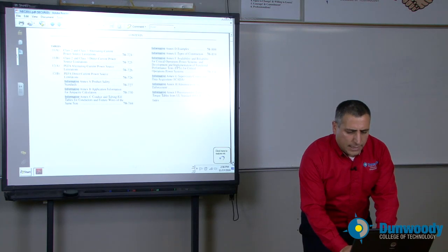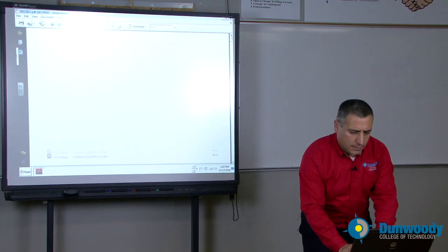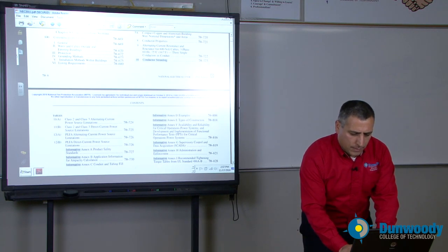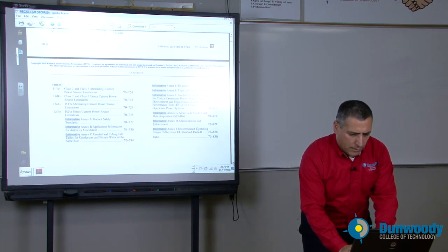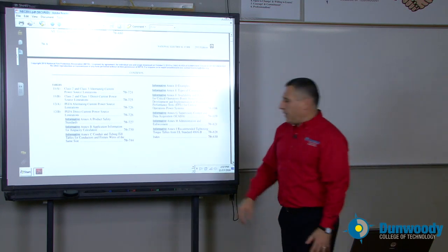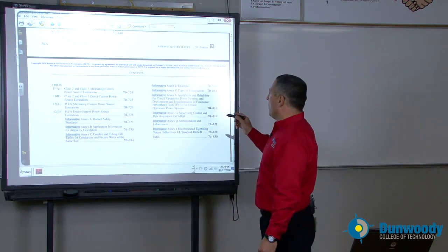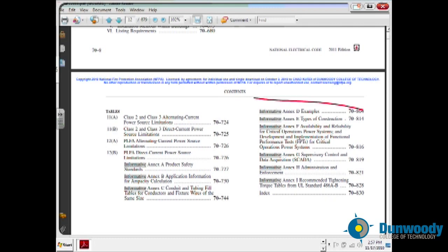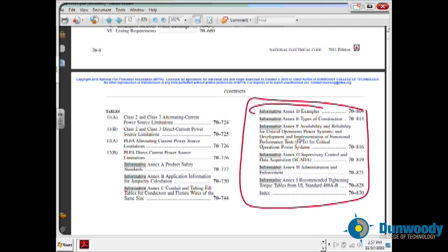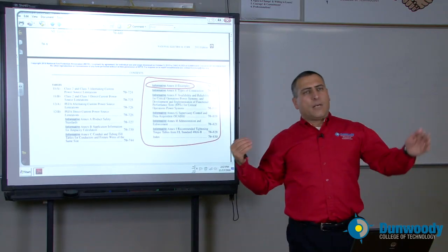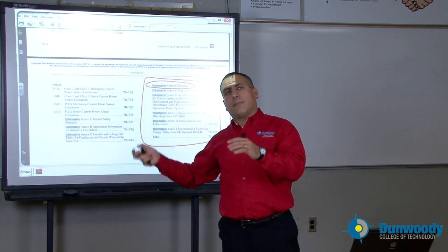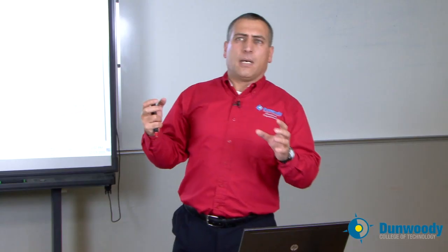Moving on into annexes — Annex A, B, and so on. Informative Annex D and E have a couple of examples. Not that important, but it's really interesting. Annex D has nice examples of calculations — for example, how to calculate a feeder for a residential or commercial building, which is extremely important. Annex C is very important too: if the conductor is all the same size and insulation, how many conductors can you fit in, say, a 5-inch rigid metal conduit? Very important in Annex C.